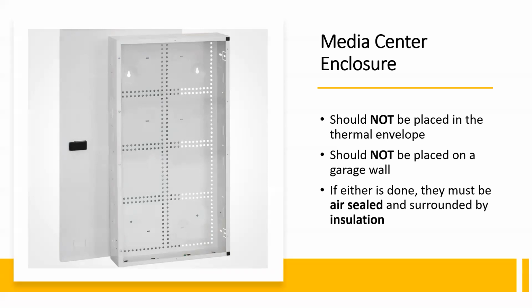So they should not be placed in the thermal envelope. They should not be on an exterior wall. They should not be on a garage wall because it's requiring you to put insulation behind it. If it's already 3.5 inches deep and it's on a 2x4 wall, you cannot get insulation behind this. This is a void in the building's thermal envelope. It needs to have insulation present behind it. So a lot of times we'd see people, if it was on a garage wall or an exterior wall, we'd ask for this to be sealed. But a lot of times the equipment installers say that's going to void the warranty because there is no air movement through the box to keep them from overheating.